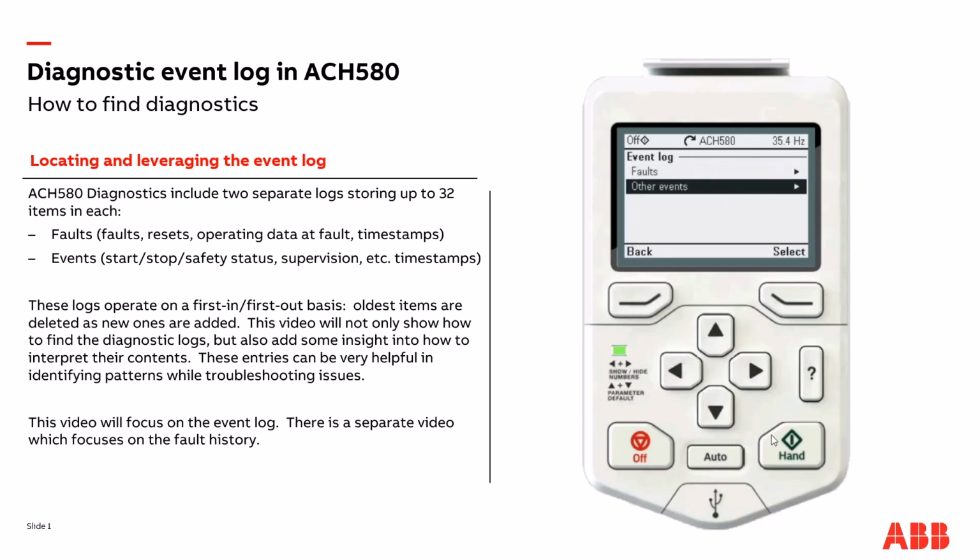So we'll back out, and now let's go to hand. Okay, so we have a set point here, and so now we're actually running. So we've transitioned from off to hand, and now let's see what events are added in the log. All right, so we see that modulating started as we push the hand button. The state transition shows up just slightly after the modulation actually started.